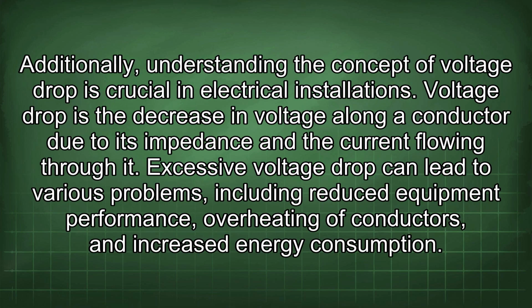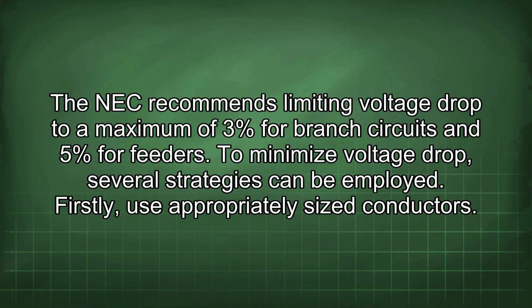Additionally, understanding the concept of voltage drop is crucial in electrical installations. Voltage drop is the decrease in voltage along a conductor due to its impedance and the current flowing through it. Excessive voltage drop can lead to various problems, including reduced equipment performance, overheating of conductors, and increased energy consumption. The NEC recommends limiting voltage drop to a maximum of 3% for branch circuits and 5% for feeders.